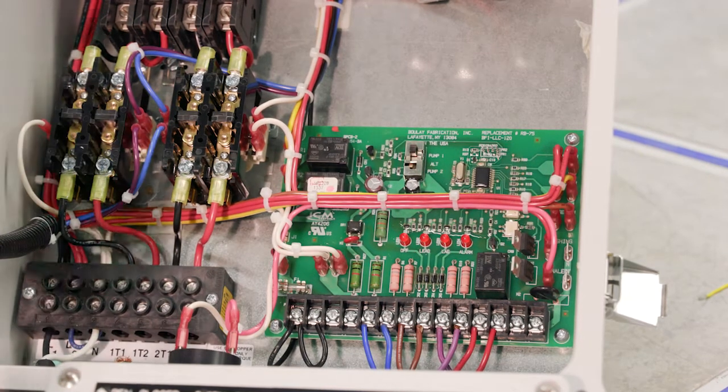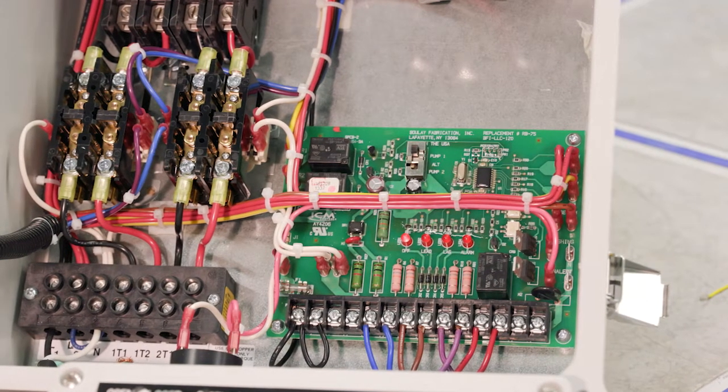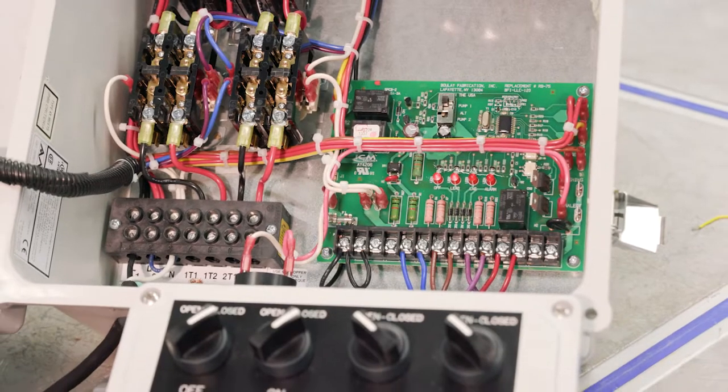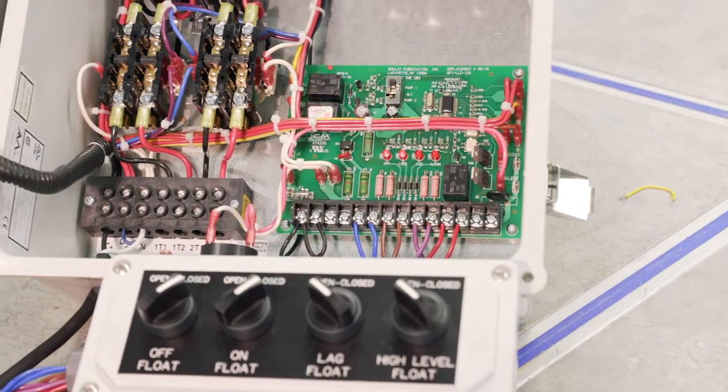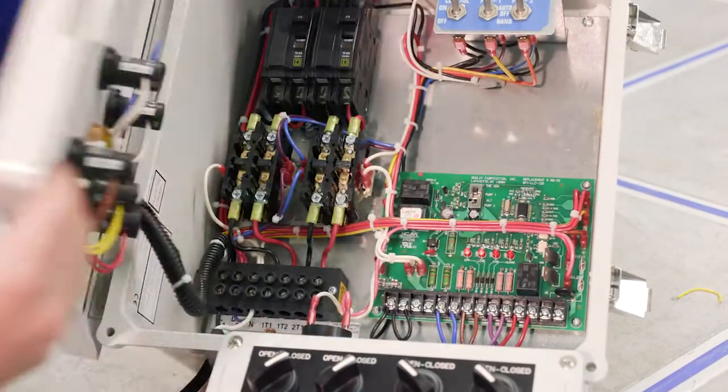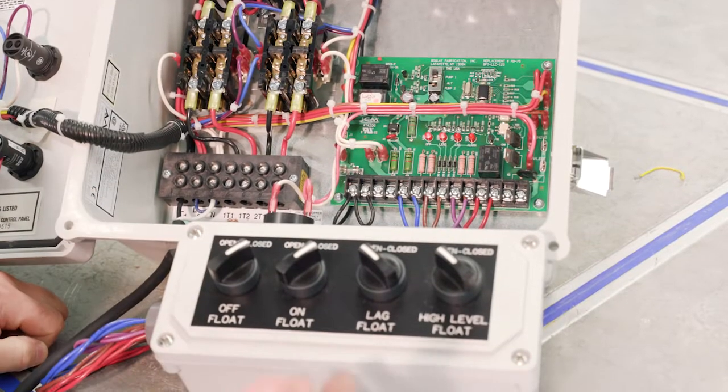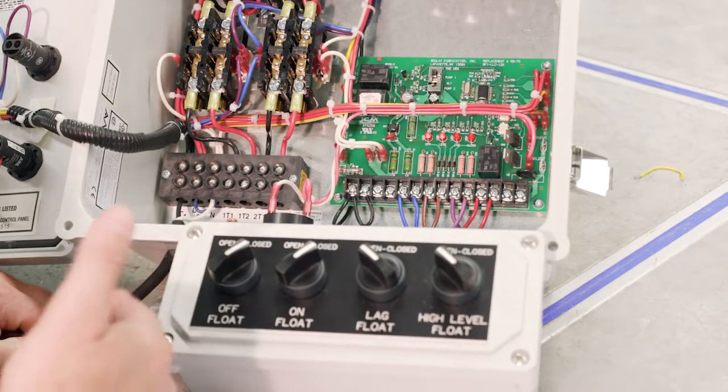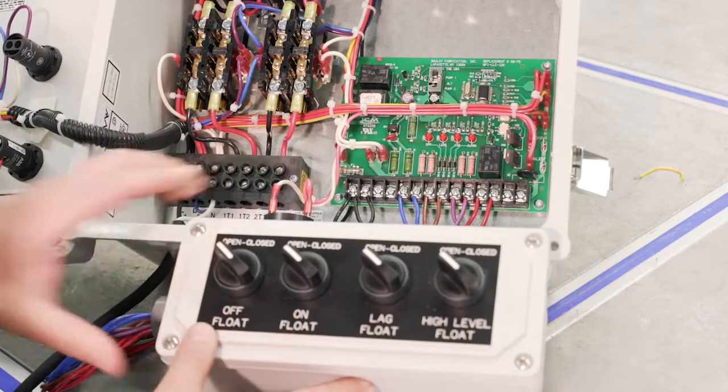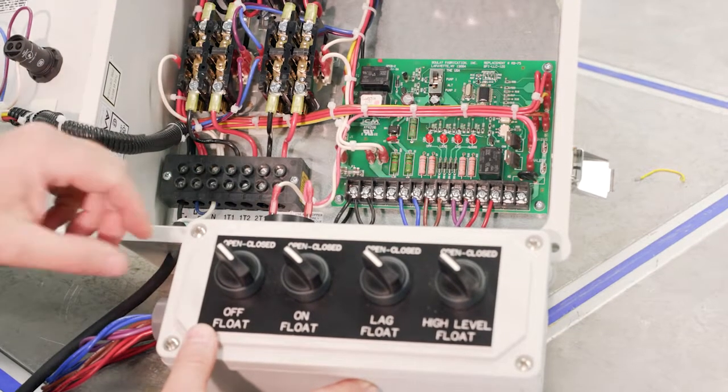So let's just take a look at that. So I've got it set to pump one, and go through our scenario again, off float, on float, let's double check. You can hear it, but pump one is running. And so really the test of that is to do another cycle, and just to make sure that it doesn't call for pump two. So we'll do that again. So there's a little delay, opens up, nothing's running right now.